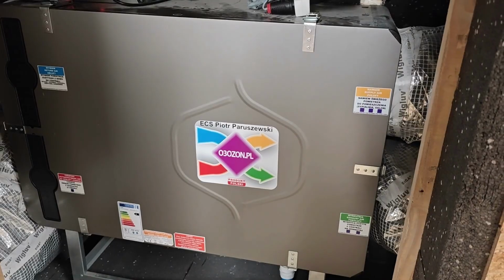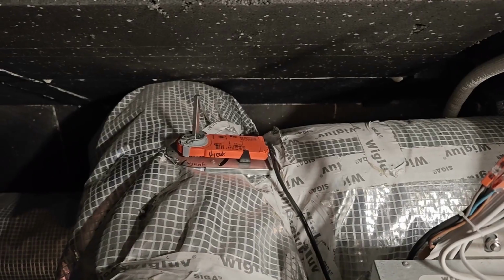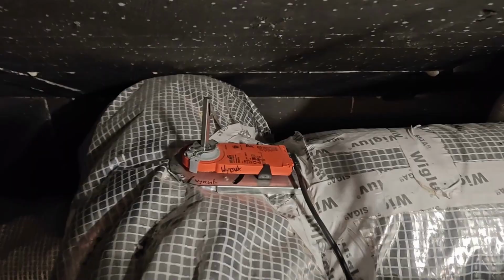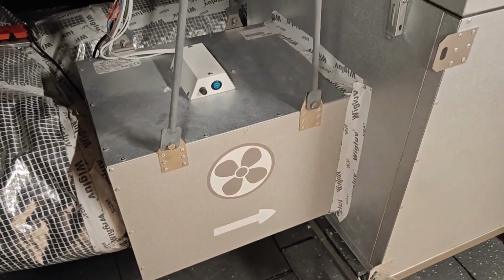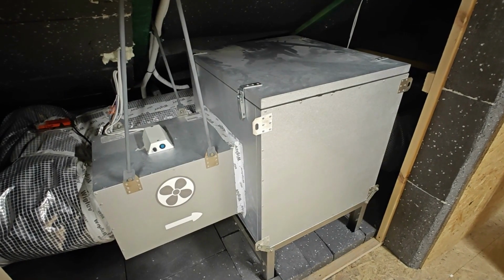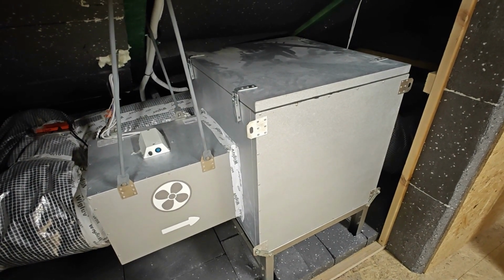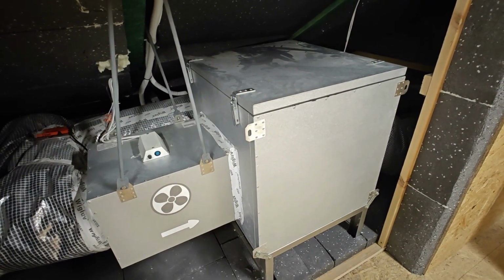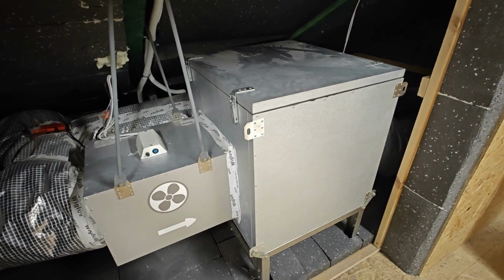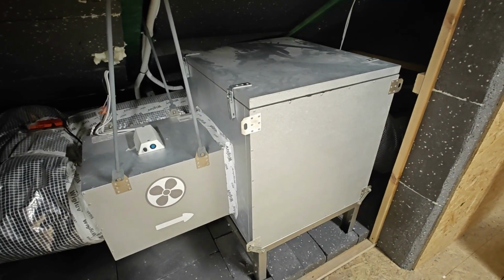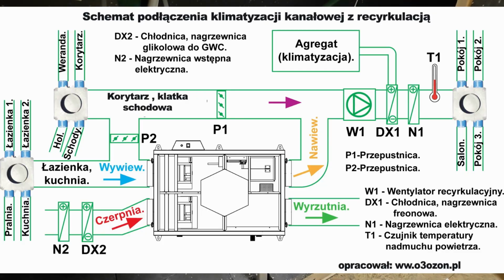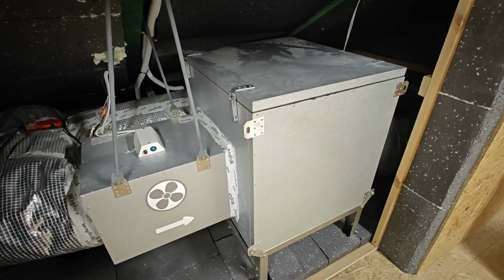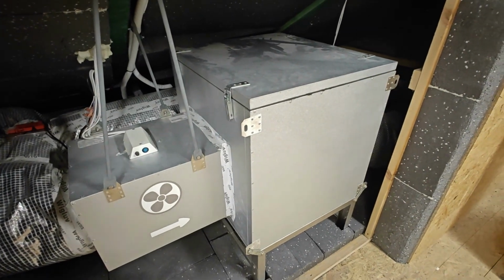The cool outside air is transported directly into the house. Behind the recuperator is a T-piece with a Belimo actuator for recirculation and the recirculation fan itself. Exhaust air removal is performed in 2 ways, depending on how the entire system operates. In the first case, all the spent air moves to the recuperator and is expelled outside. This is the standard operation of recuperation. In the second scenario, when either heating or cooling is engaged, a portion of the air from the exhaust room, specifically those like wardrobes and communication corridors, is returned to the fresh air intake before the refrigerant heat exchanger, which is situated in this very spot.